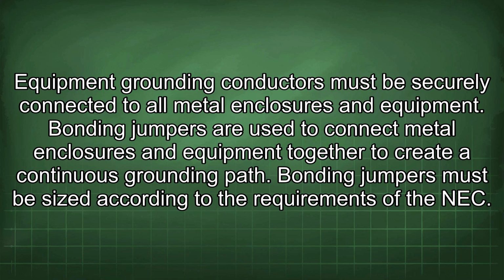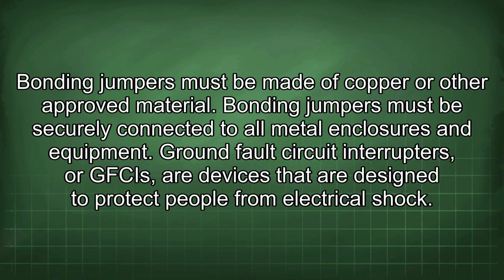Bonding jumpers are used to connect metal enclosures and equipment together to create a continuous grounding path. Bonding jumpers must be sized according to the requirements of the NEC. Bonding jumpers must be made of copper or other approved material. Bonding jumpers must be securely connected to all metal enclosures and equipment.